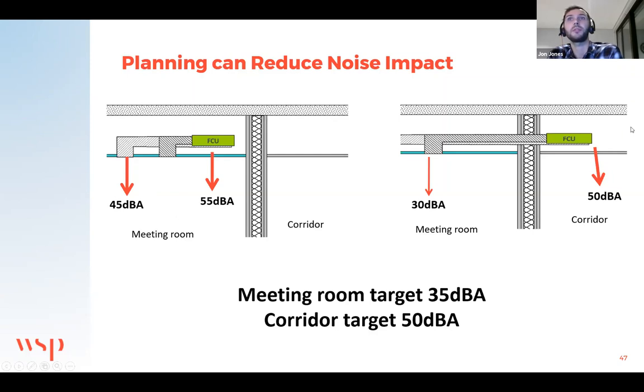in the meeting room. If you switch the arrangement to something like we do have on the right, actually then with the fan coil unit out of the room, one, you have a less sensitive corridor and potentially a plasterboard ceiling, which isn't penetrated with the ductwork in. This then splits up the noise sources, so it can be more achievable to hit the noise targets in these areas. Furthermore, with the increased length of ducts, this could potentially be lined. There's more scope for introducing attenuators if needs be, or just acoustic lining, to make sure that this internal noise level in the meeting room, which would be considered a sensitive space, can be achieved.